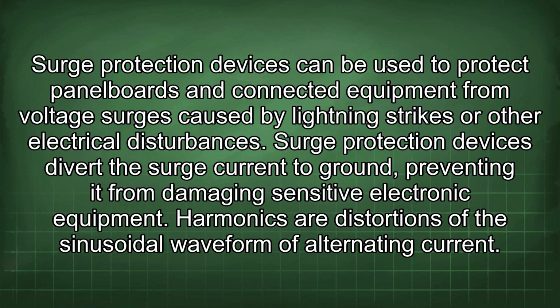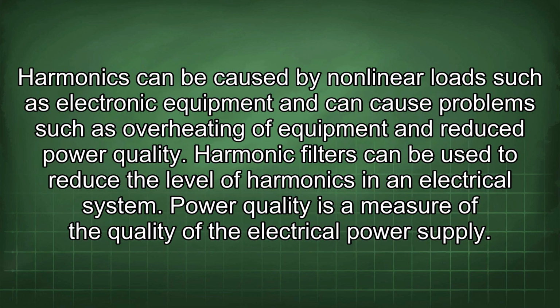Surge protection devices can be used to protect panelboards and connected equipment from voltage surges caused by lightning strikes or other electrical disturbances. Surge protection devices divert the surge current to ground, preventing it from damaging sensitive electronic equipment. Harmonics are distortions of the sinusoidal waveform of alternating current. Harmonics can be caused by nonlinear loads such as electronic equipment and can cause problems such as overheating of equipment and reduced power quality. Harmonic filters can be used to reduce the level of harmonics in an electrical system.